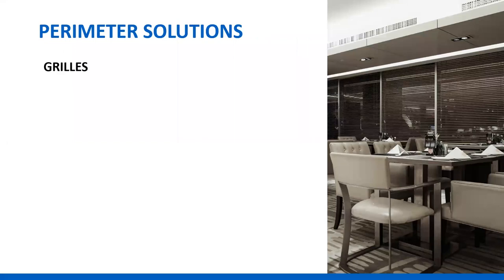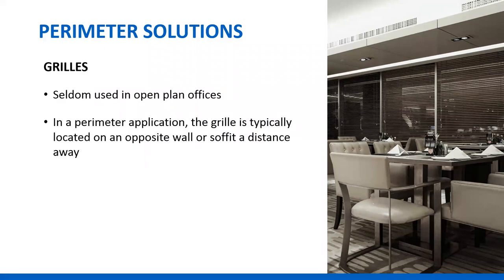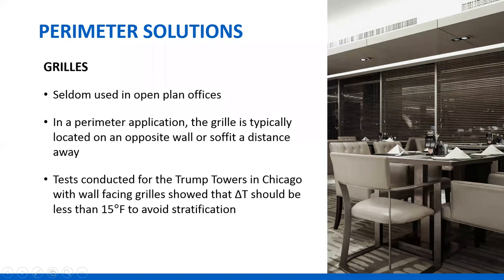Sometimes we see grills in the perimeter. In this example, the grill is in the soffit blowing away from the window — probably not ideal. More often we'll see a grill located in a soffit opposite the window blowing towards the window — we like that a little better. Trying to calculate the performance of a grill is complicated because the blades on the front can be adjusted, or as in the photo, they may be randomly adjusted, which is most often the circumstance you'll see in the real world.